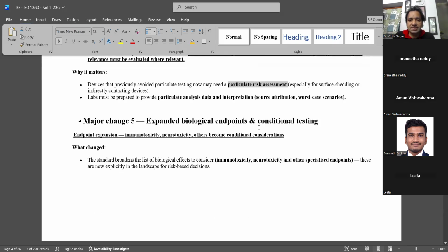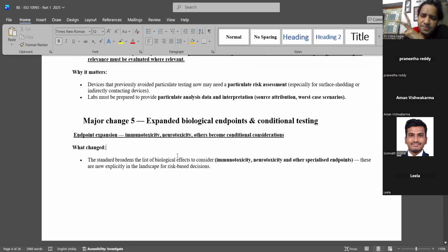Okay, expanded biological endpoints and conditional testing. See, this is what I said. Now your endpoints will expand on a lot of things: contact time, duration, particulate matter, okay, risk management, and totally you need to restructure into your 10993-1 flow diagram. Okay, duration of contact, in which tissue it is contacting, and they have also added something like immunotoxicity, neurotoxicity. But these are very difficult, like only in behavioral studies you'll know neurotoxicity, and that too in an animal model. Very difficult to do in vitro. It can be done in vitro on certain neuronal cell lines, like rat neuronal cell lines. We can know whether they are causing any neurotoxicity or degradation of myelin sheath.